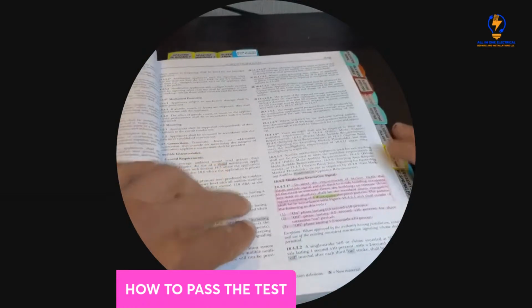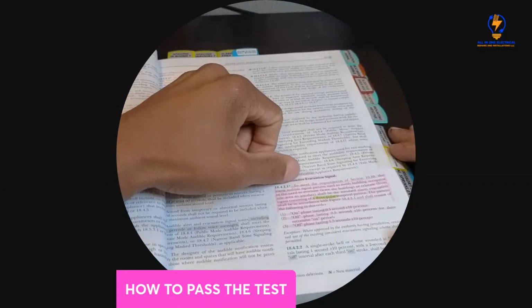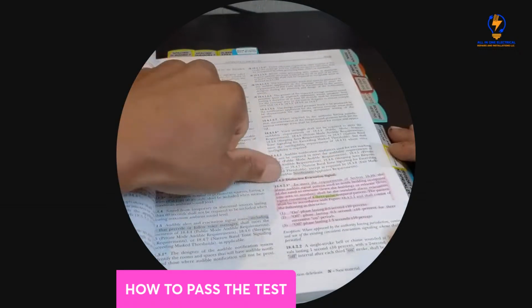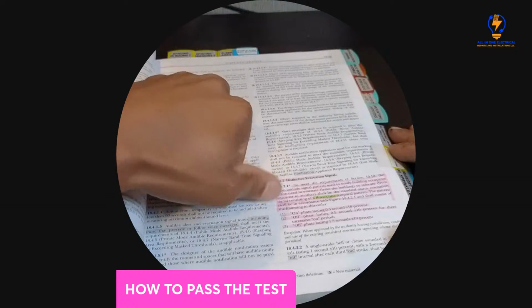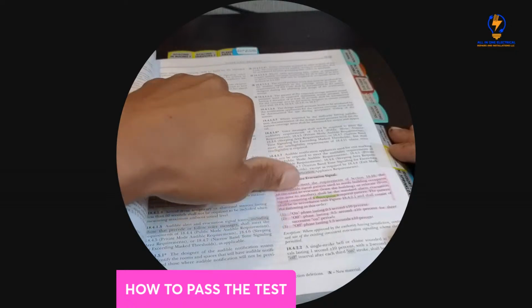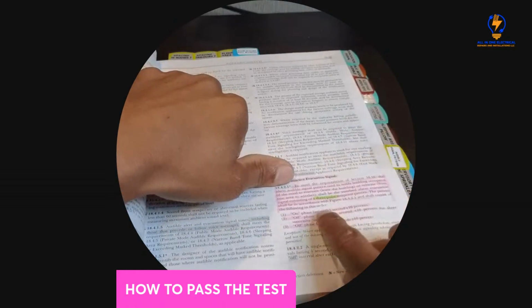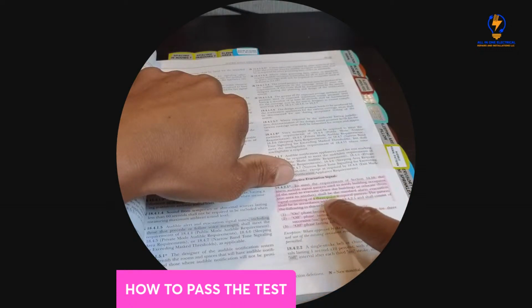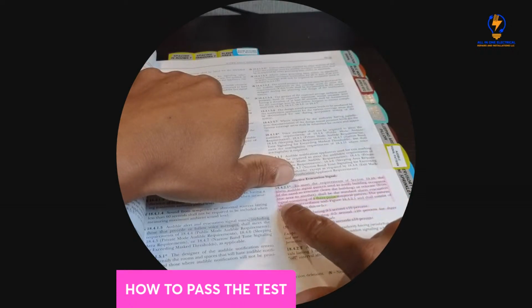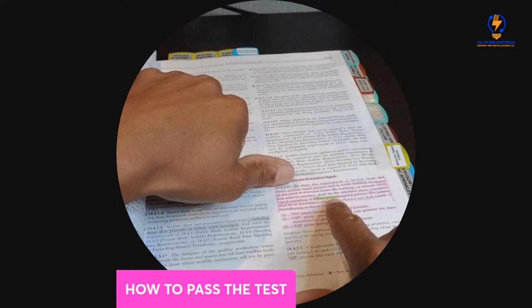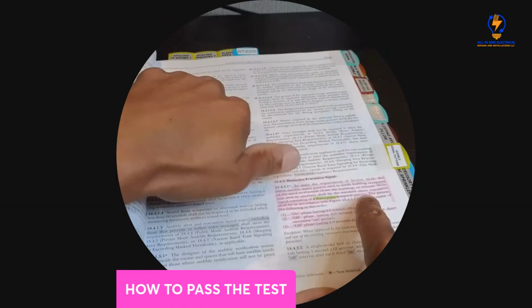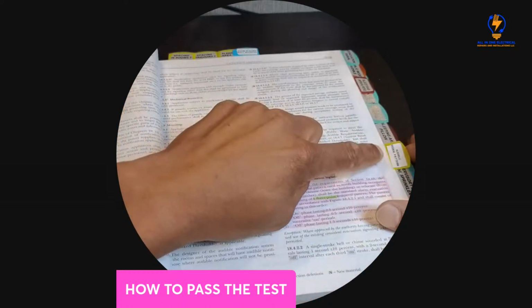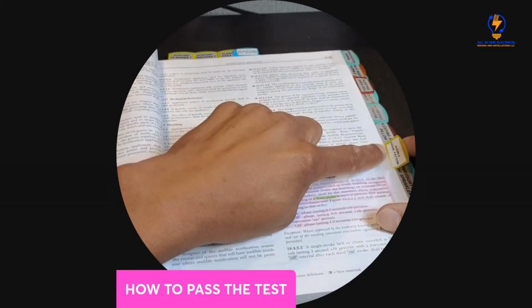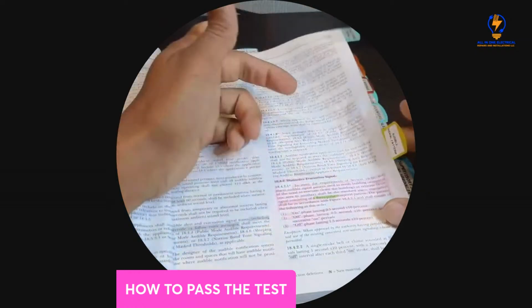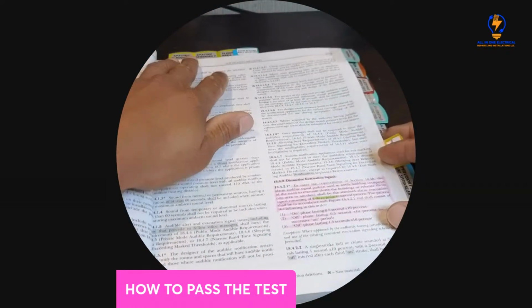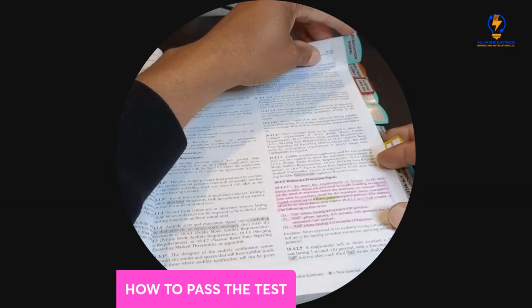Okay, so we move along and we go on page 115. Hopefully you can see this, we are at 18.4.2, distinctive evacuation signals. And then this first and basically second paragraph right here. Very important, it shall be the standard alarm evacuation signal consisting of a 3 pulse temporal pattern. Very important here. So I put as a tab audible signal pattern. Okay, that's page 115. And then another tab over here, which is evacuation signal.